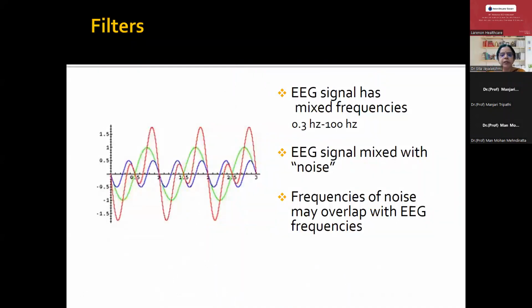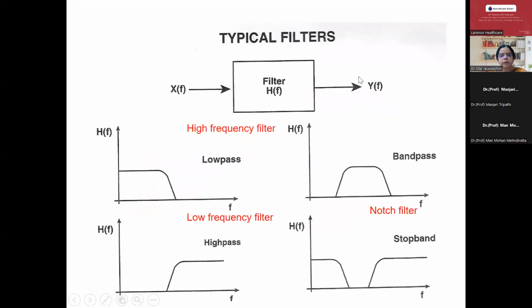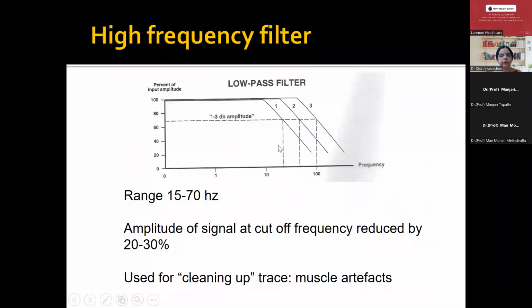Why do you have a high frequency and a low frequency filter? Usually the EEG signal is below 70 Hertz and above 1 Hertz. The high frequency filter is also known as the low pass filter, and the low frequency filter is known as the high pass filter. In addition, we use something called the notch filter. So let us come to this. First is the high frequency filter. Usually we keep it around 70.